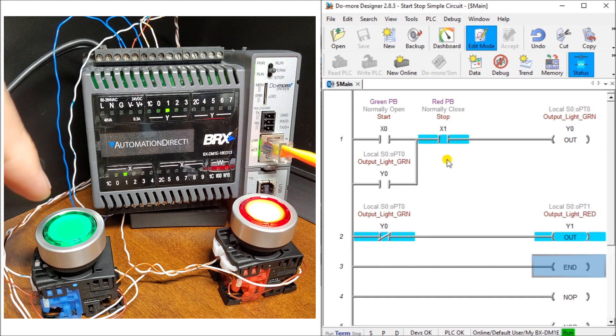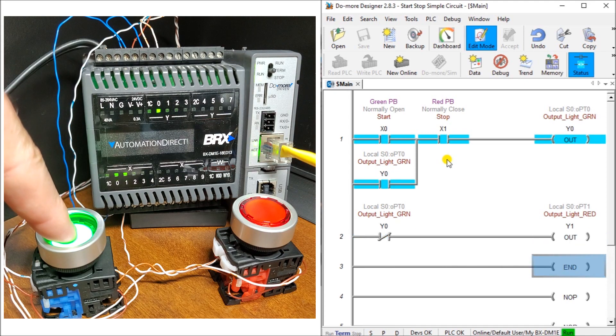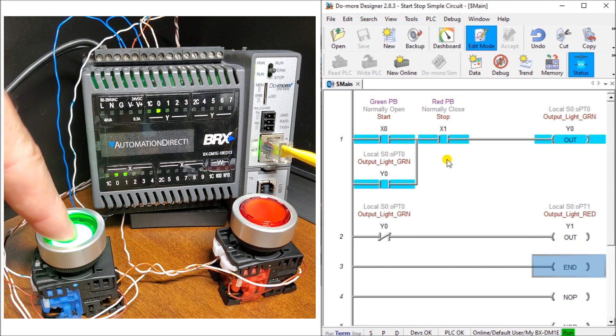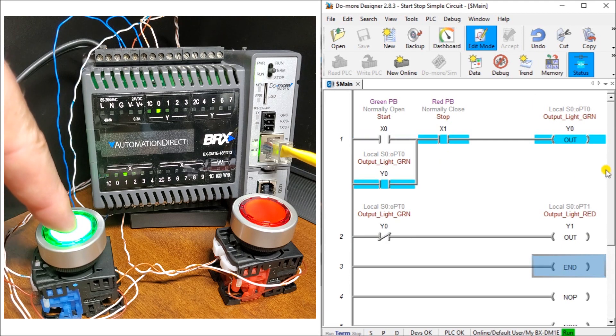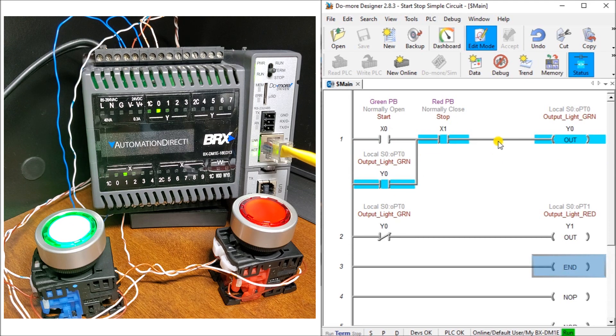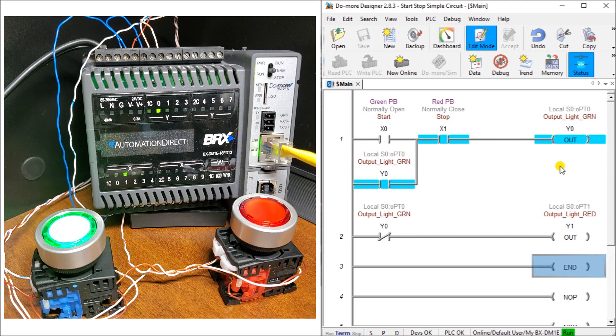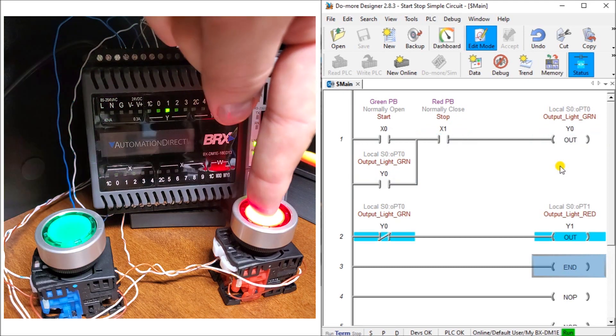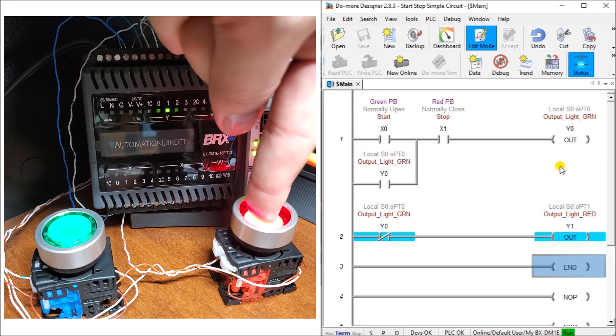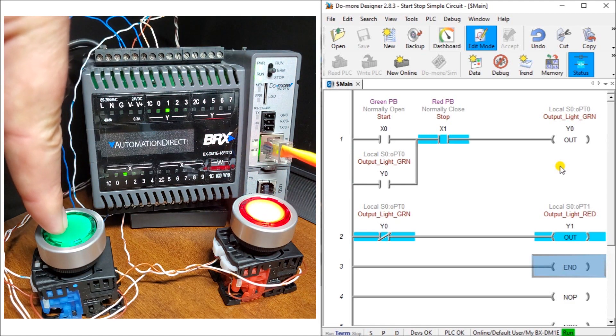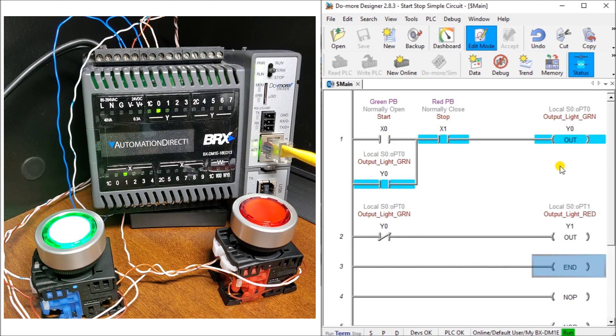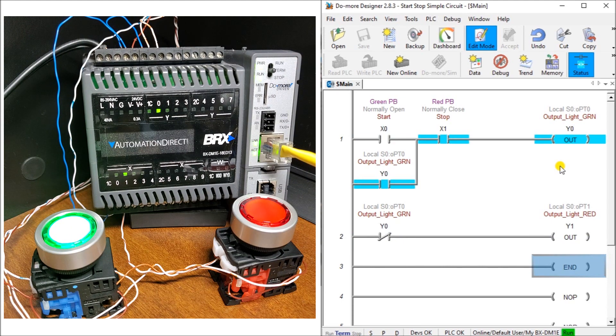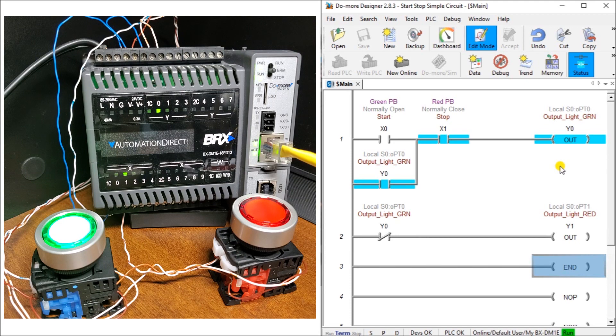I can visually see this by using online monitoring. If I hit the green push button, you can see how it highlights over, turns on my green light. I let this go. It turns off here, but seals it in. So I still have my green light on. Going back to my red, I can then stop that. Start it again. So online monitoring of our PLC really helped in aiding looking at this information and determining what is wrong. So if I had a switch not working or I had a light not working, I quickly determined what that was.